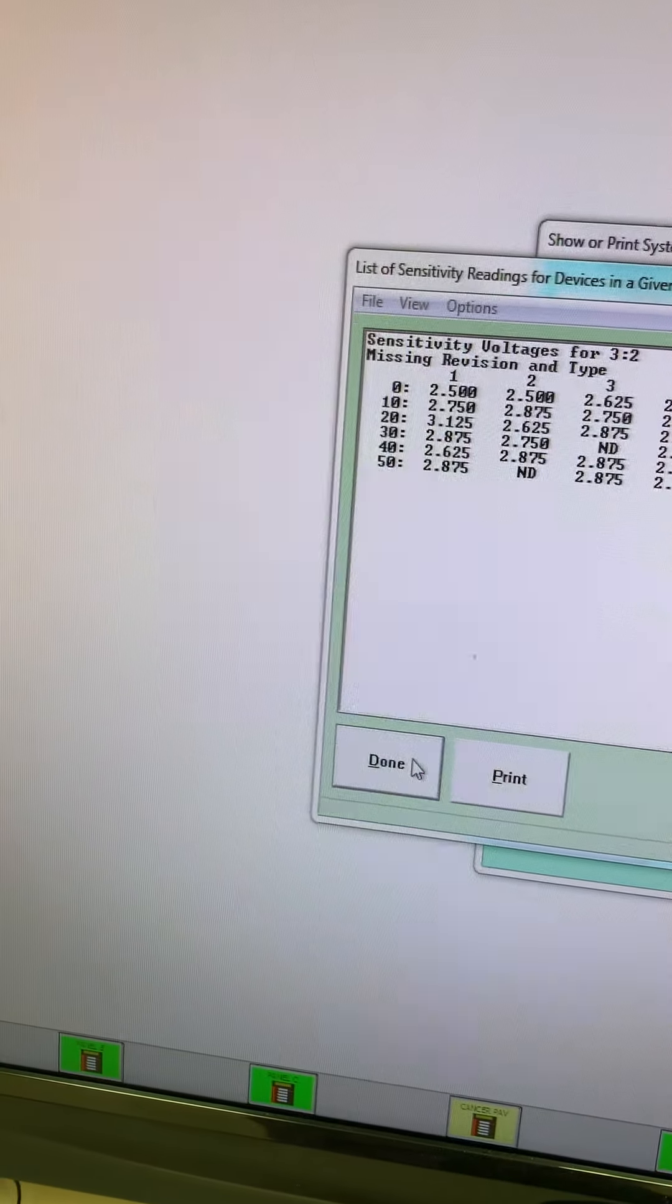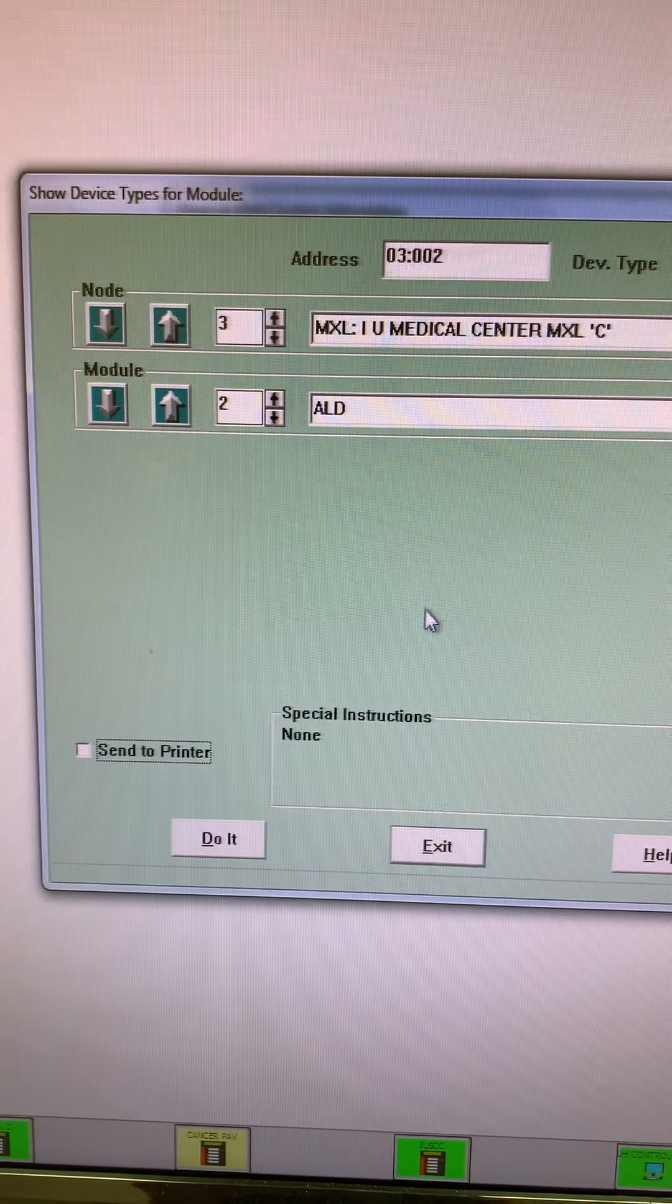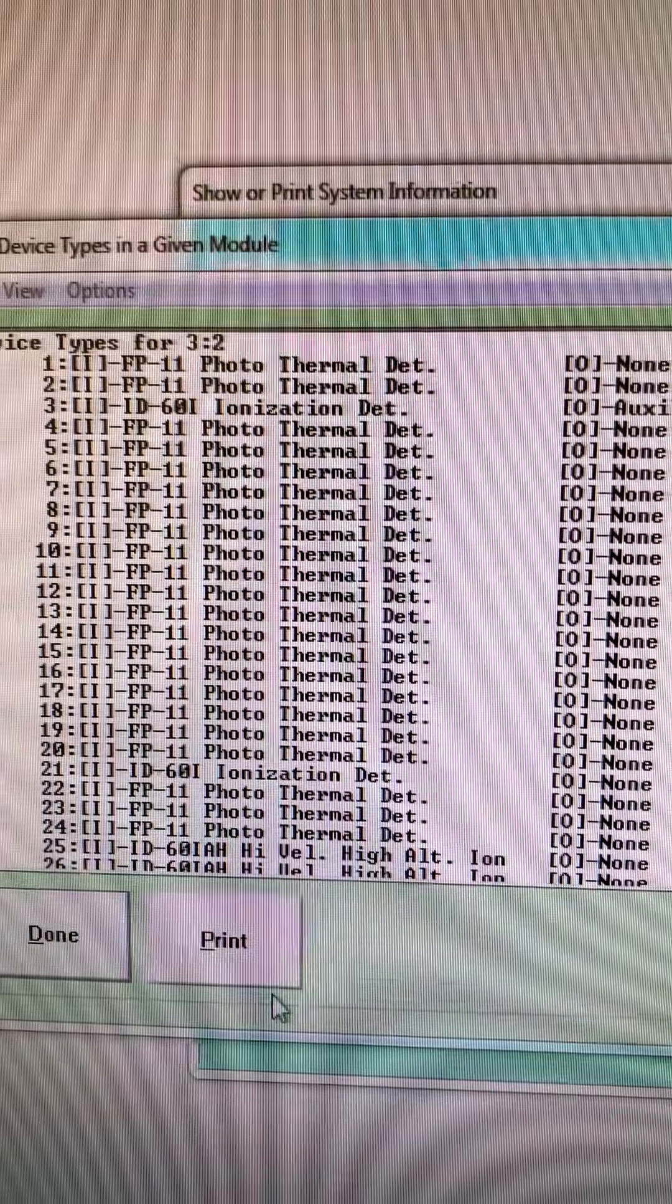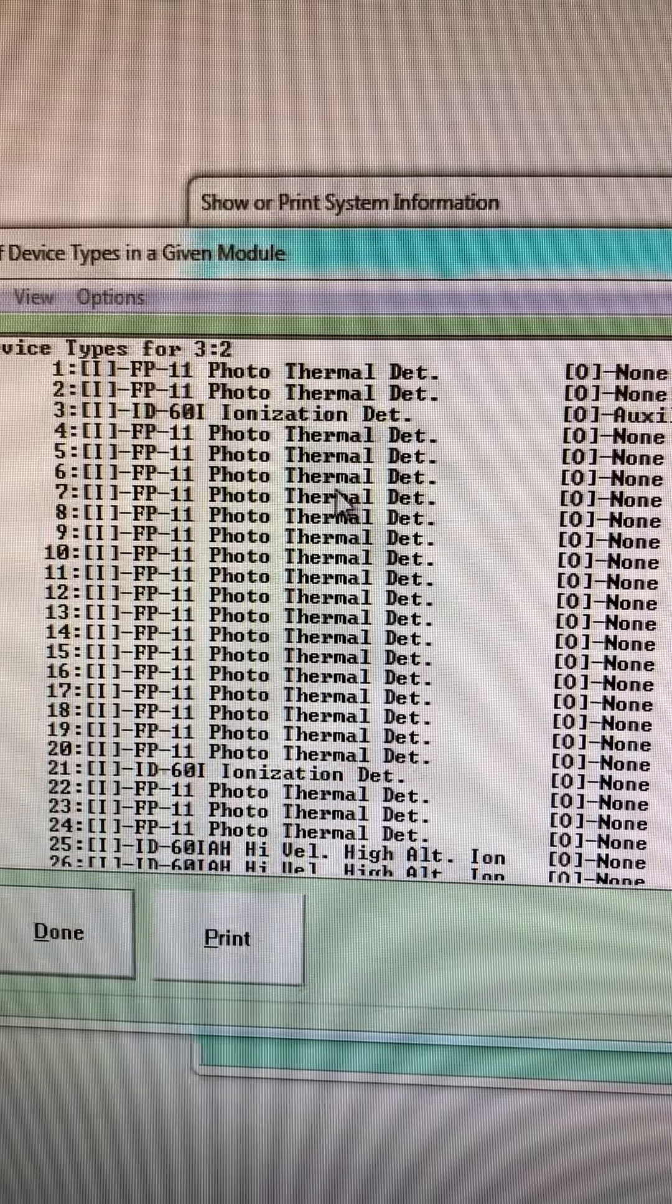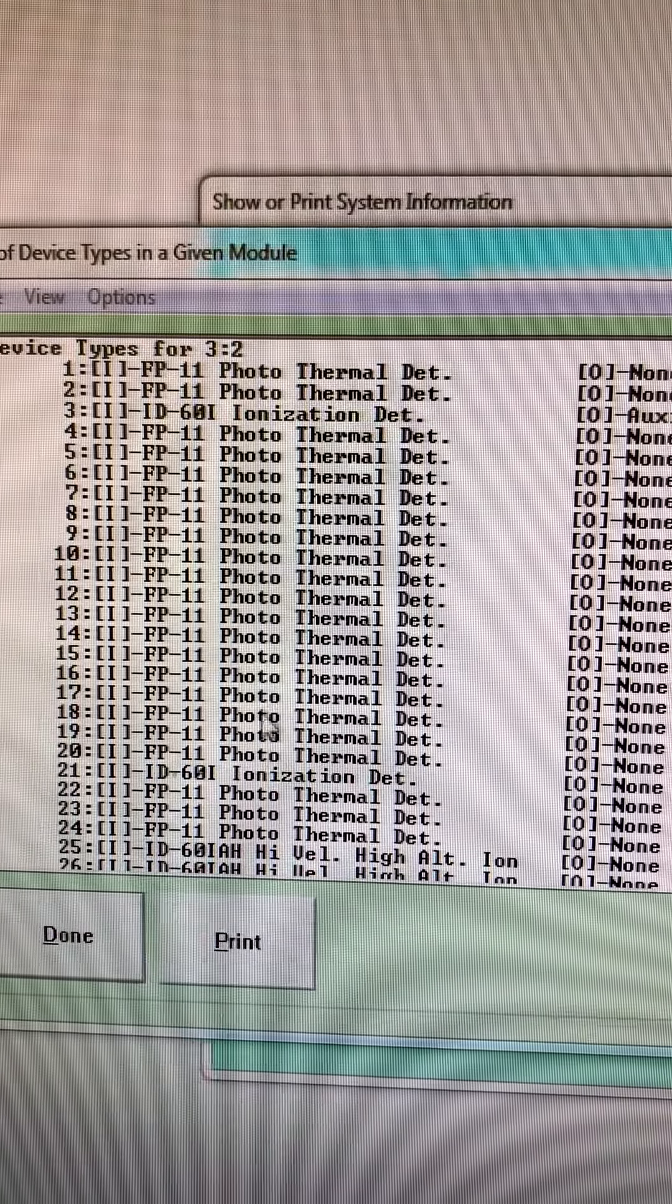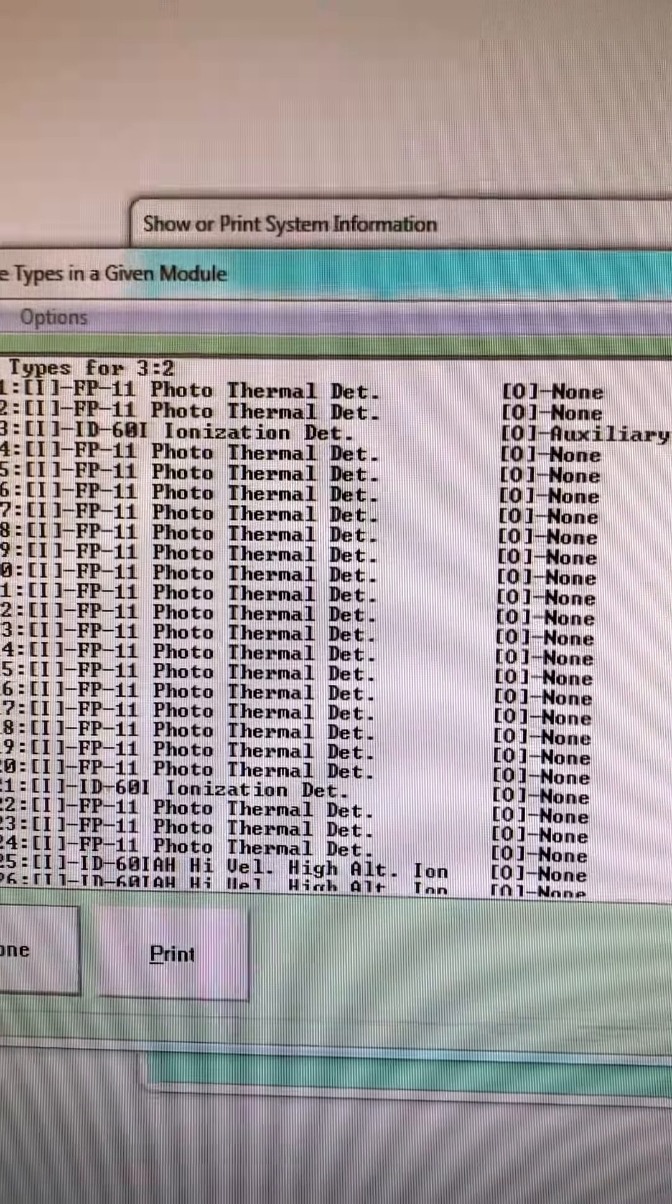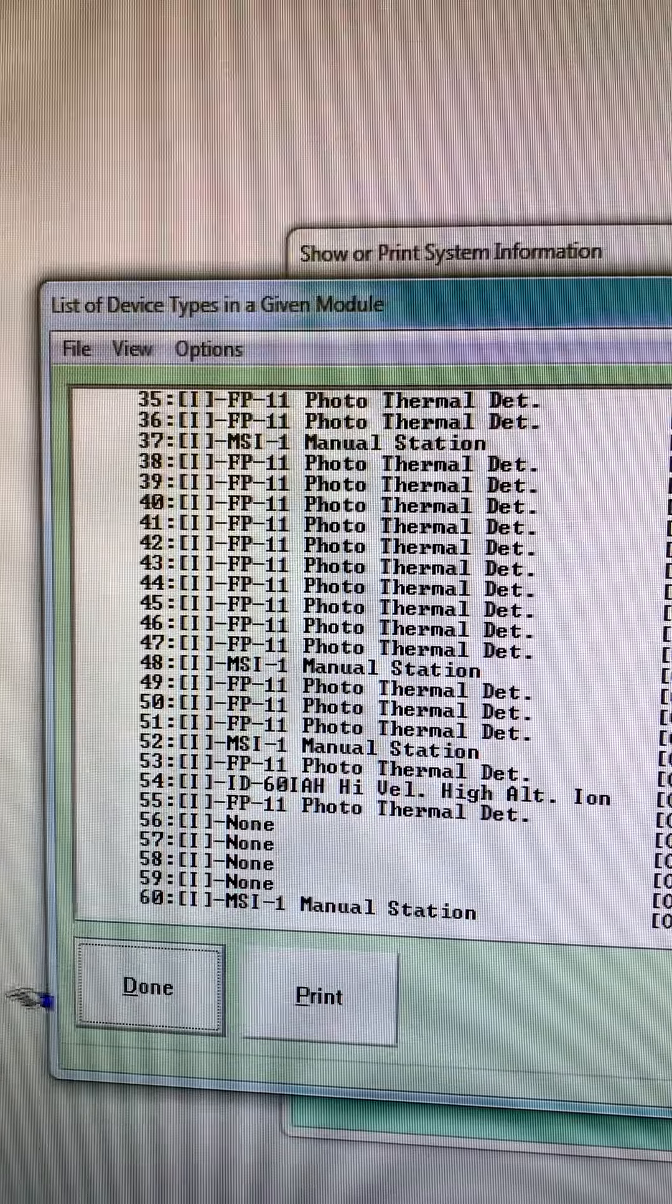Click Done here. Another thing here, look at device types. You basically get a list of all the devices. We can do this loop by loop and it will tell us. So loop two in the same panel, Panel C loop two, we get a list of all the different devices that we have: photo thermal detectors, tells us what type of detector it is, FP11 which is the newer MXL detectors. We've still got an ID60 which is one of the older ionization detectors. I can scroll through that as well.